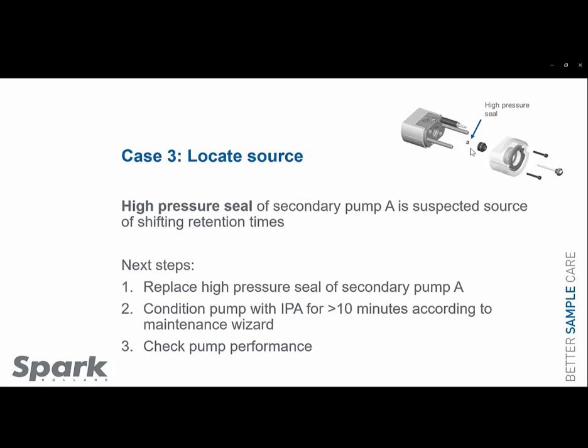We suspect the high pressure seal in the secondary pump head of pump A. We will replace this high pressure seal. After replacing the high pressure seal on pump A on the secondary pump head, we will condition the pump using 100% IPA with a back pressure of at least 200 bars for 10 minutes. After this conditioning step, we will check the pump performance.